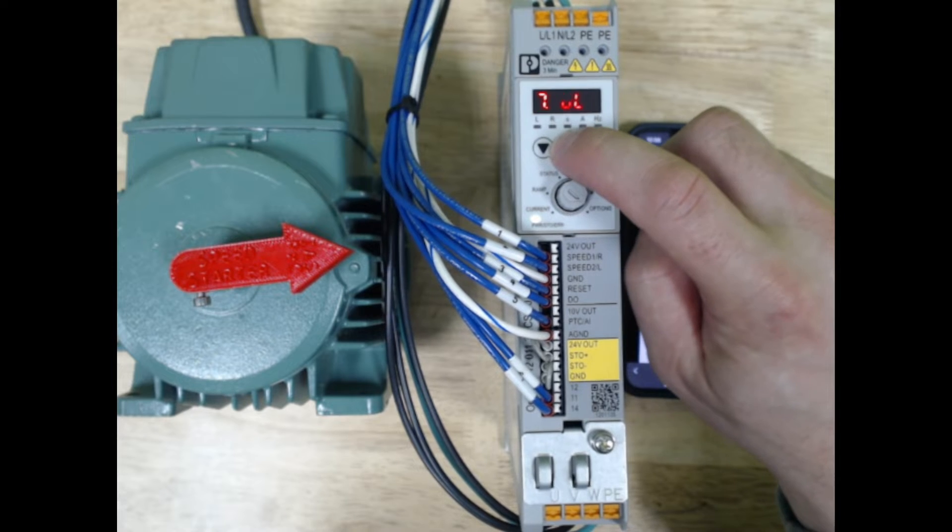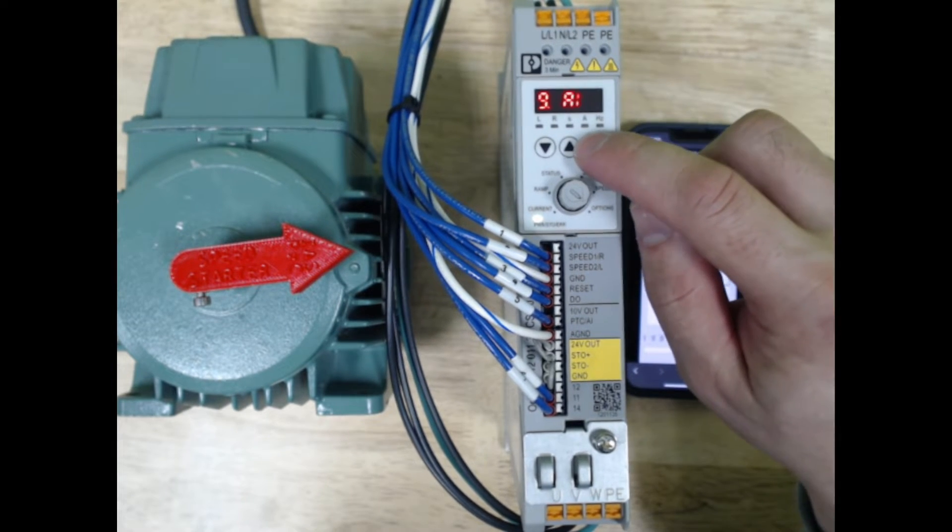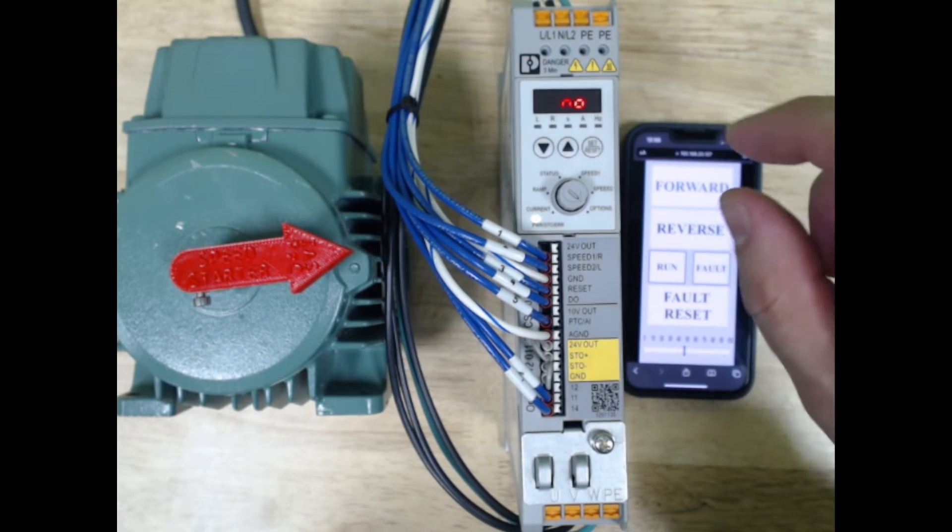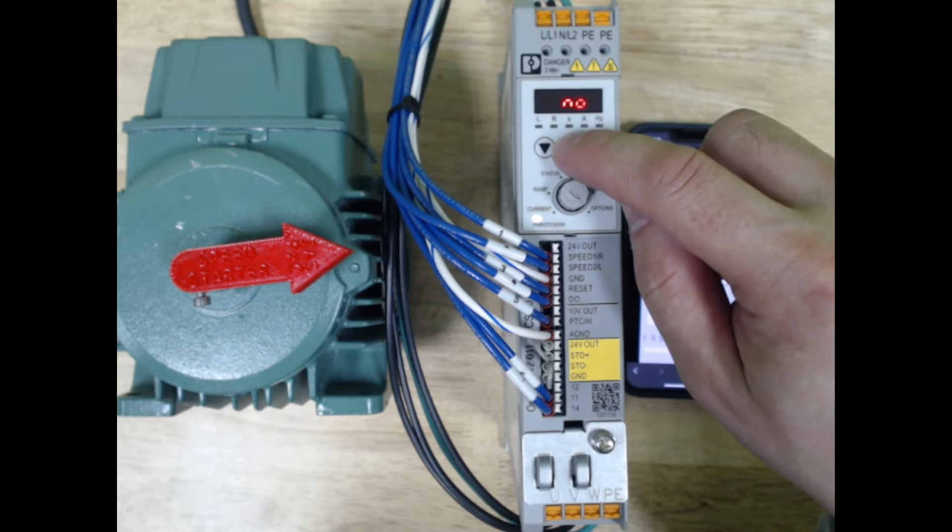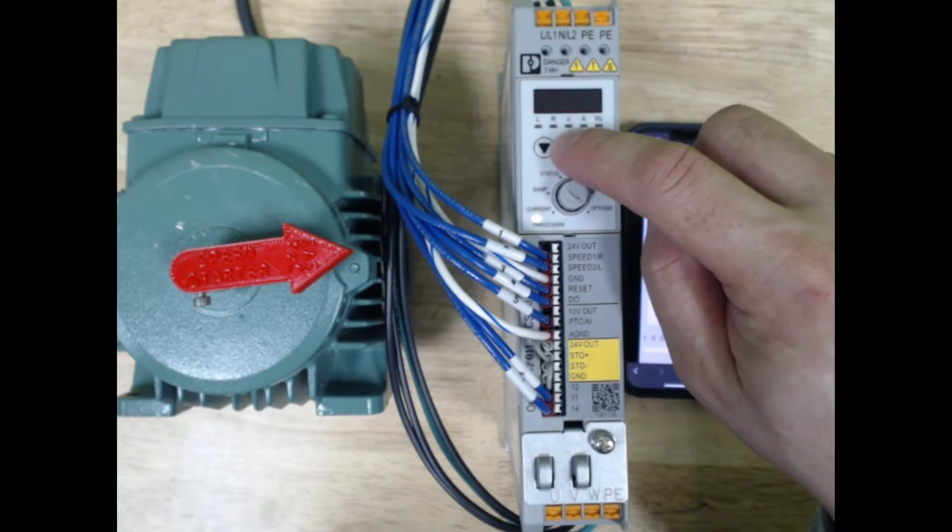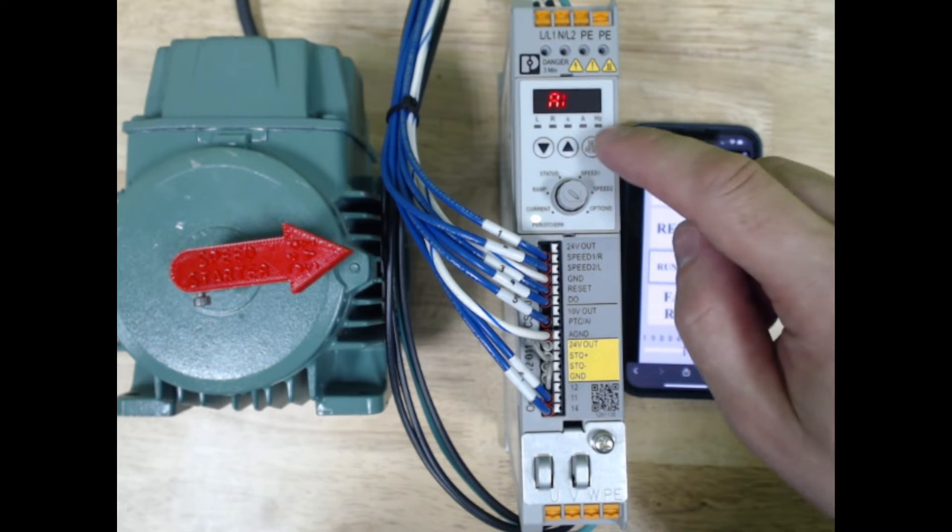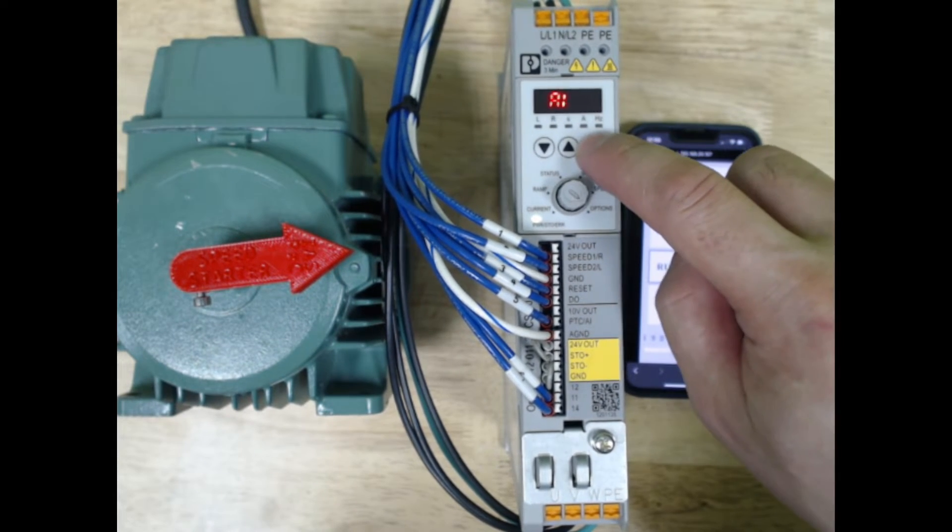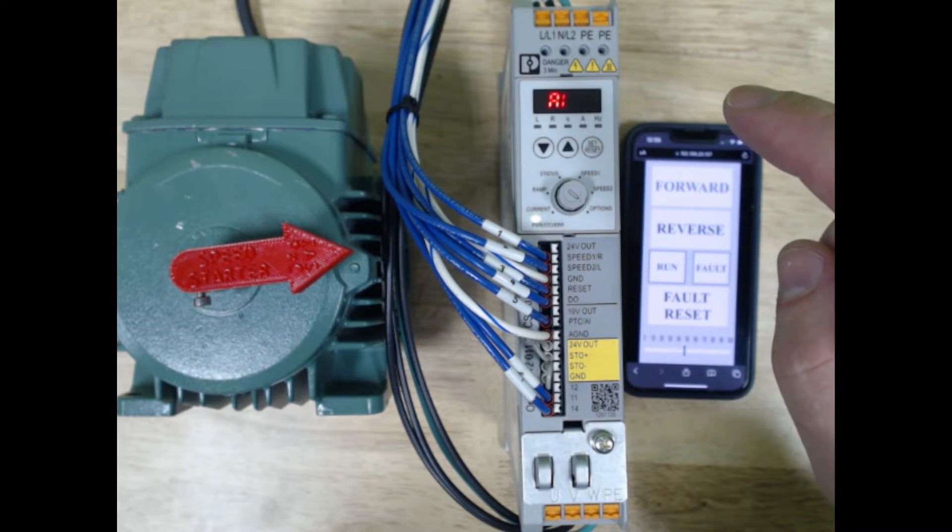We're going to go to number nine. Number nine is going to set up the analog input. Right now it's set to none. We have a couple of PTC options for the motor, but we're just going to use the analog input. So we select analog input.